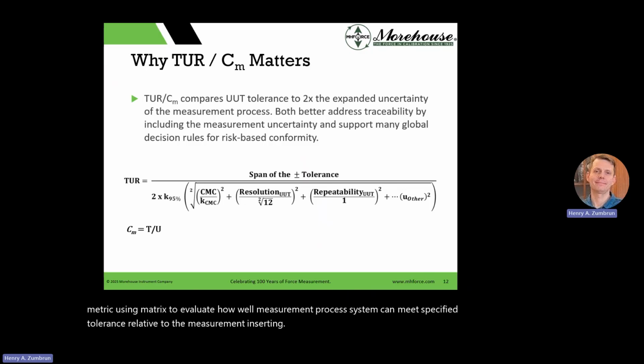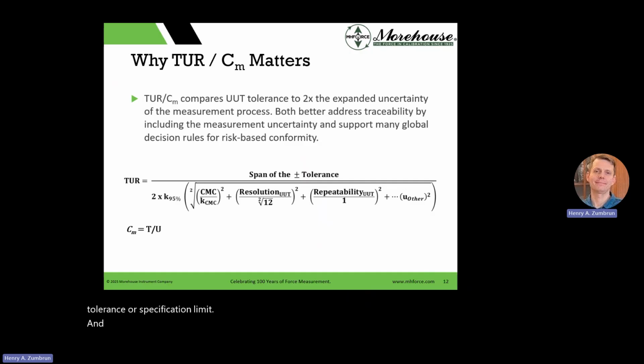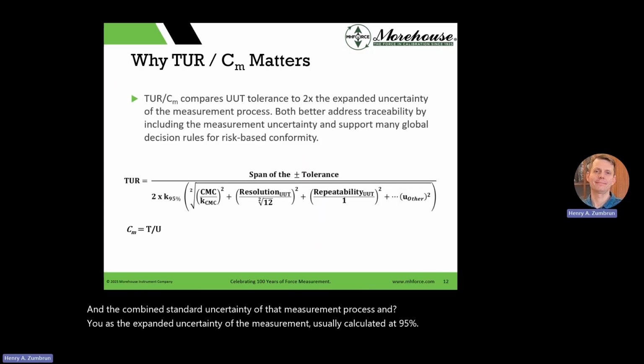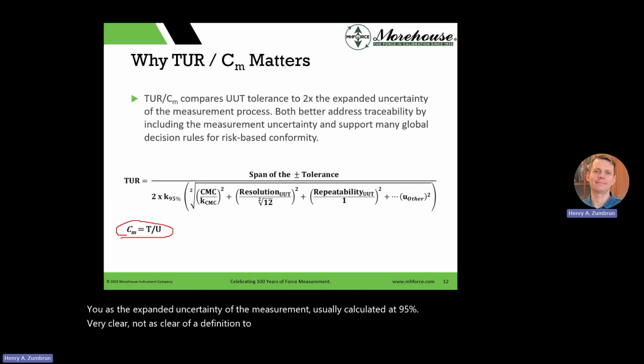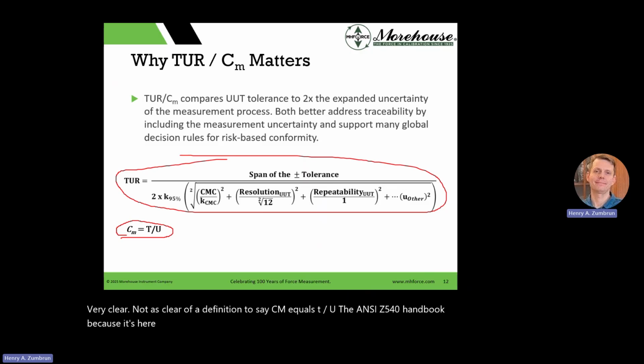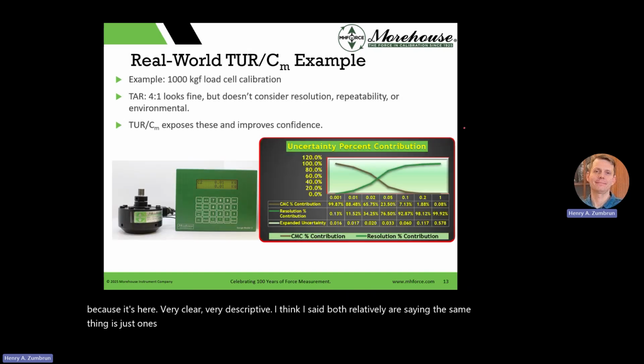According to JCGM 106, this index assesses the ratio between a given measurement's specified tolerance or specification limit and the combined standard uncertainty of that measurement process. And U is the expanded uncertainty of the measurement, usually calculated at 95%. The ANSI Z540 handbook is a very clear, very descriptive definition, not as clear as just saying CM equals T over U. Like I said, both are relatively saying the same thing. It's just that one is a lot more descriptive and breaks it out.